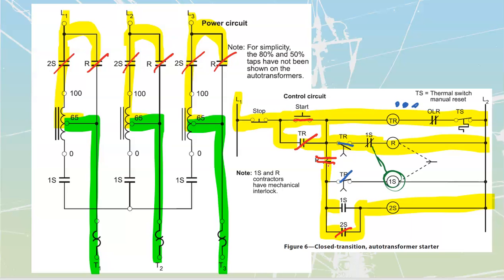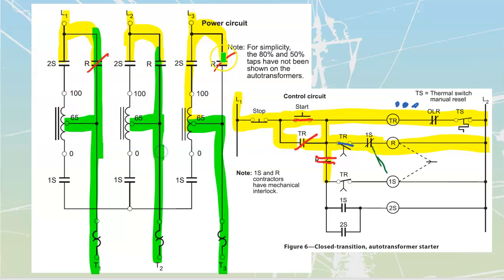And when that happens, it's going to open this setup down here. It's basically going to depower everything that was down below here. At that point, it's going to lose power, which means that all of this 2S that we have up top here are all going to lose power, but that's all right because we've already got this R path closed and we have current traveling through to the motor itself.